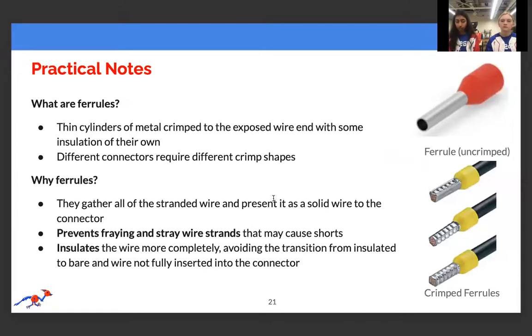Some more practical notes about ferrules: they are thin cylinders of metal crimped to the exposed wire with a little insulation of their own. Different connectors require different crimp shapes. We use ferrules because they gather all the stranded wire and present it as a solid wire to the connector, preventing fraying and stray strands that may cause shorts. It also insulates the wire more completely, avoiding the transition from insulated to bare and wire not fully inserted into the connector.